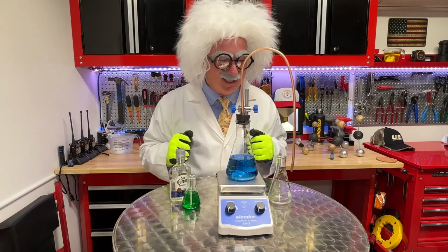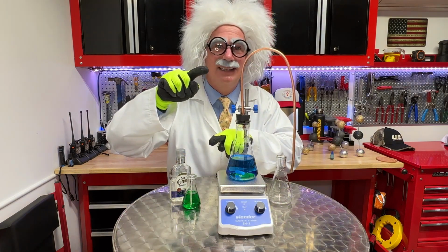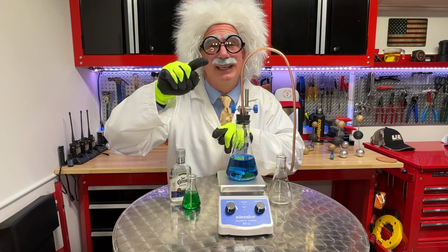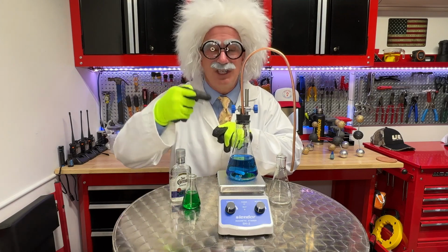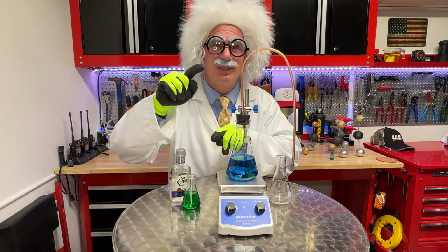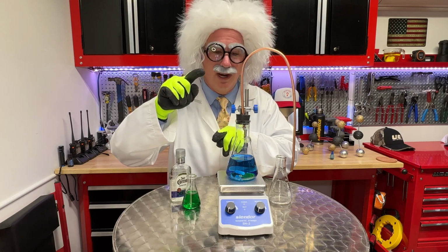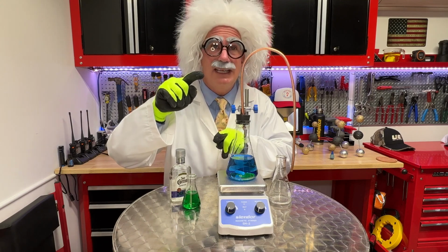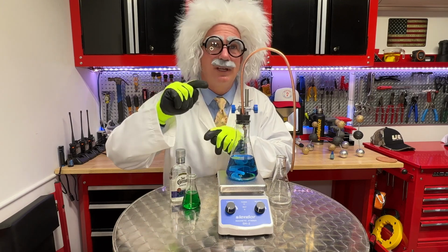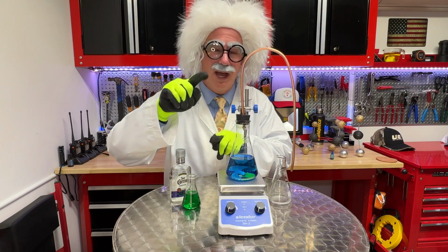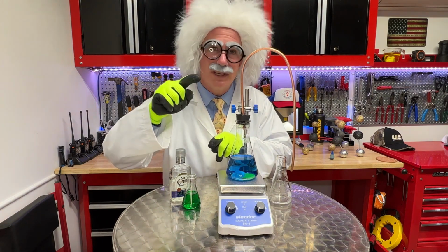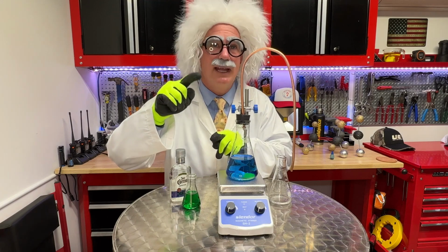The fundamentals of glide, where we have a bubble point and a dew point, and we have a potential for fractionation or separation of our chemicals in between. So be aware that best practices would say if we have a leak in the vapor portion of our system and we're not 100% sure did we have fractionation, it's always best practices to replace refrigerant and add new.